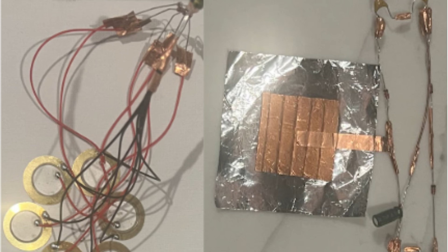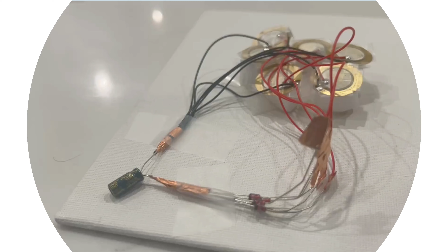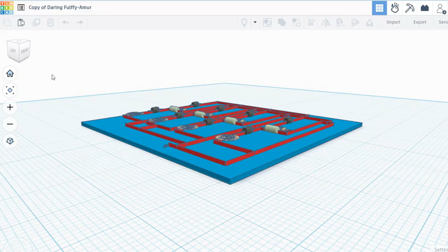So, I engineered the first hybrid wireless energy harvesting system combining focused ultrasound and ambient radio frequency waves to permanently power low energy implants. We generated an average of 53 microwatts, exceeding the 10 to 50 microwatts requirement for a standard pacemaker. Our key innovation is this circular pattern design. It tackles angular and transverse misalignment. Even if the external transducer shifts, multiple piezoelectric discs remain in optimal contact and maintain energy output.